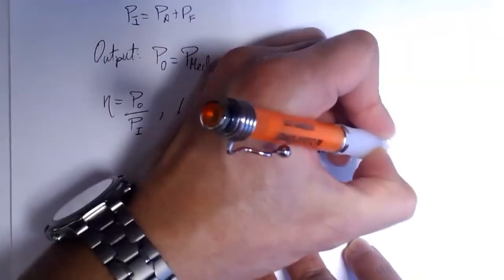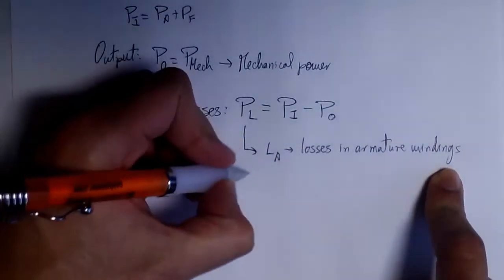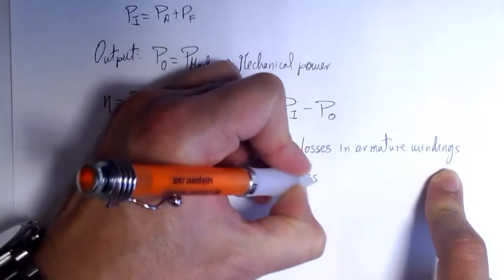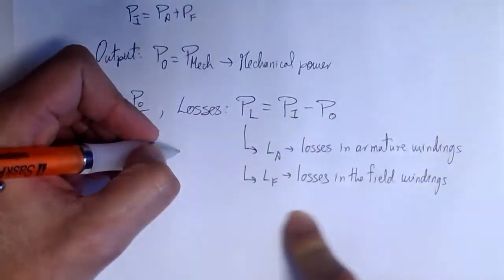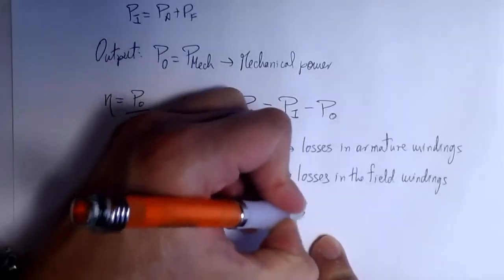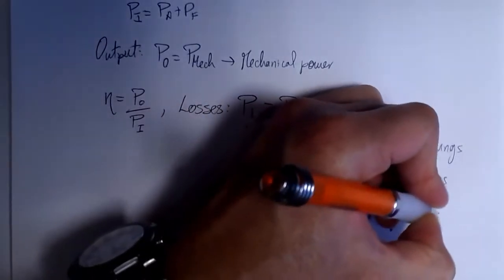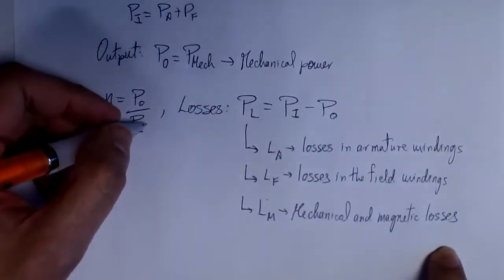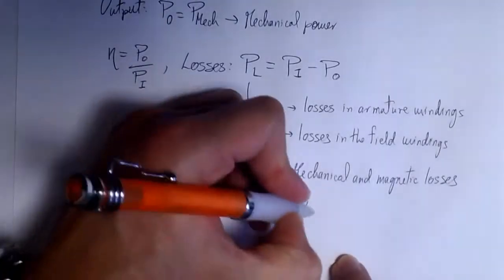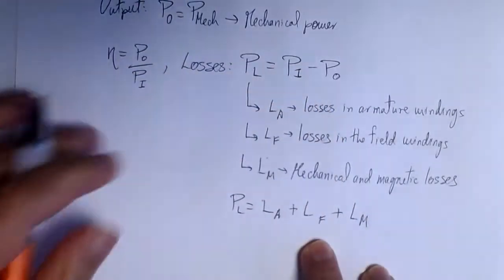There are in general three types of losses. First, electrical losses in the armature windings — some power is dissipated by the wire there. Second, power dissipated in the field windings, which we call LF. And finally, mechanical and magnetic losses, such as friction. The total losses PL can be computed as the sum of losses in the armature windings, losses in the field windings, and the mechanical losses.